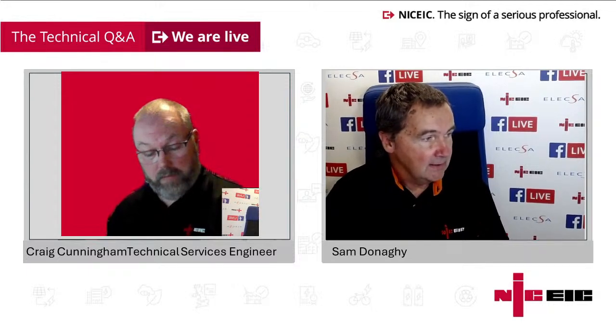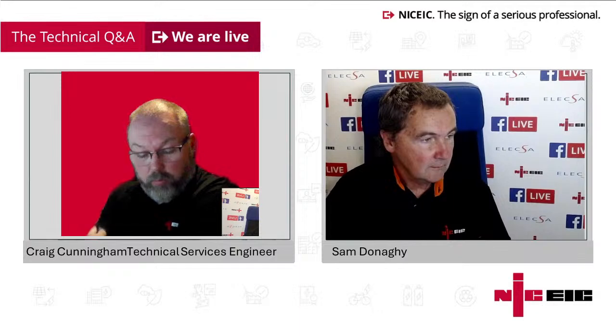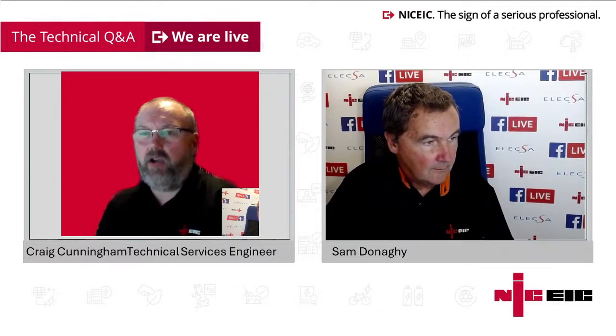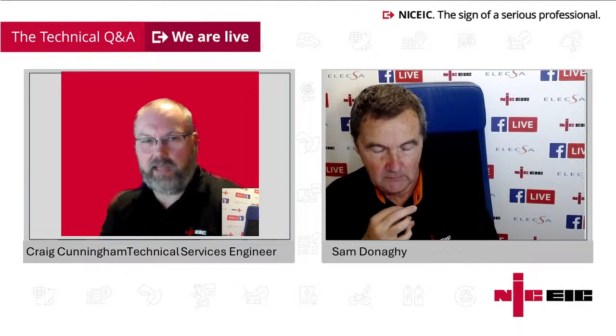Anything you'd add to that, Craig? No, I agree with that completely. The only thing, that was from an EICR point of view. If it was from an initial verification point of view, then I'd be referring to regulation 133.1.1 and 133.1.3. That refers to selection of equipment, so it normally says about British or European standards, etc. If it falls outside of that, then the designer, the person who's installing it, has to provide information on their certificate that it is suitable. So it may be classed as a departure, if you like. No, spot on. It's very different whether we're looking at this from an EICR or from a design and installation certificate following verification.